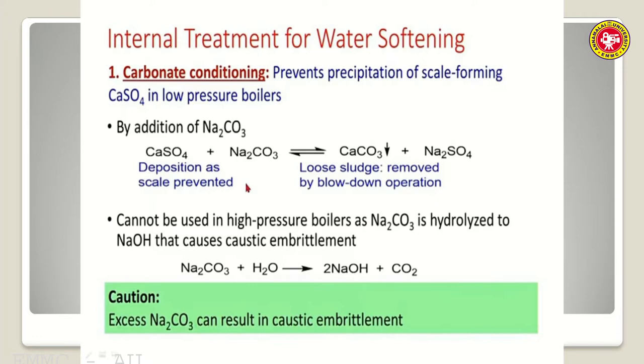Carbonate conditioning is simple: calcium sulphate is present in hard water and will form scales. So you add a calculated quantity of sodium carbonate. The calcium sulphate, which would form a hard-to-remove scale, is converted into calcium carbonate, which is a loose sludge that can be removed by blow-down operation.